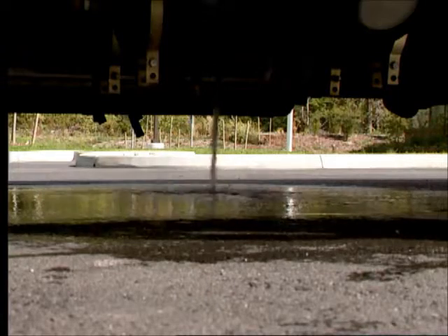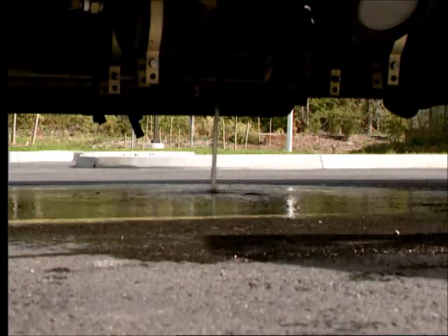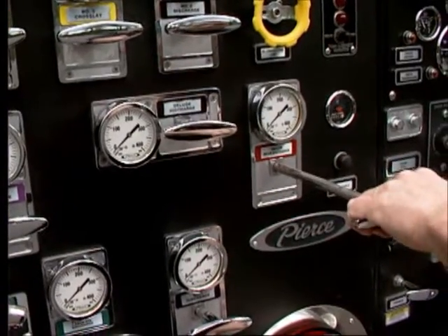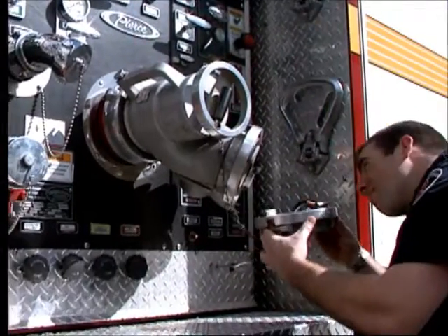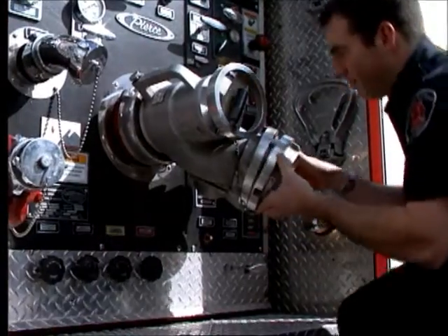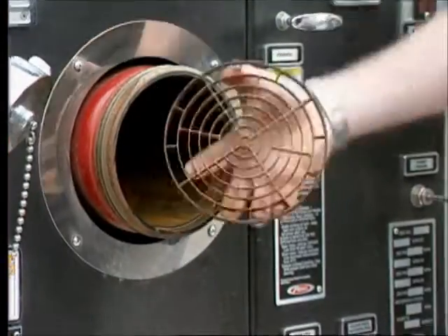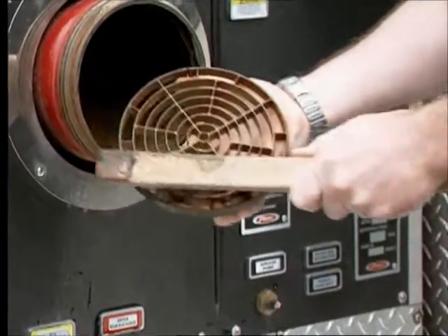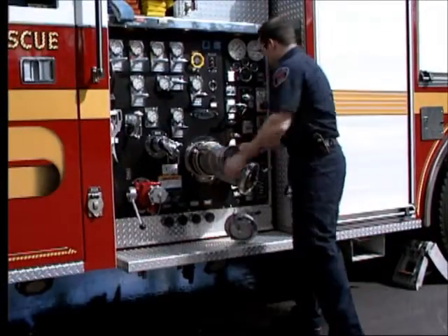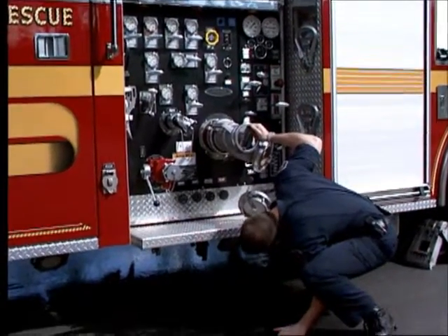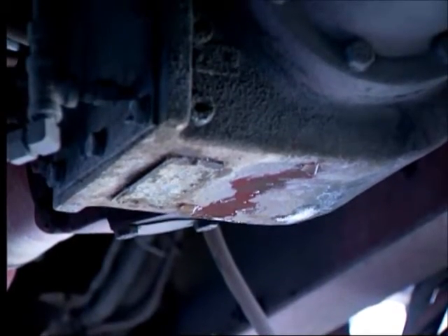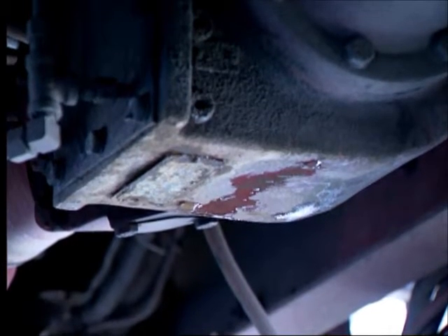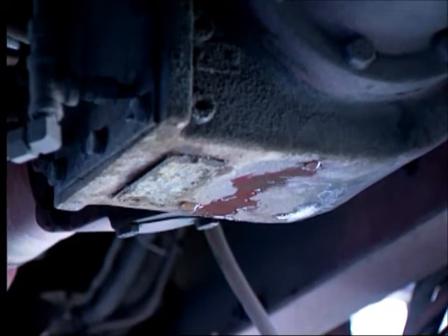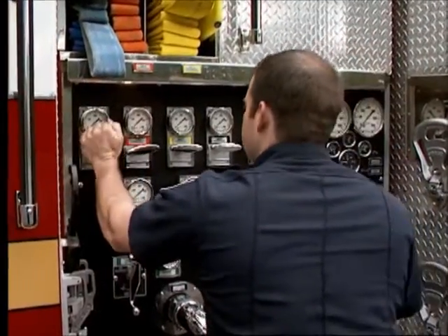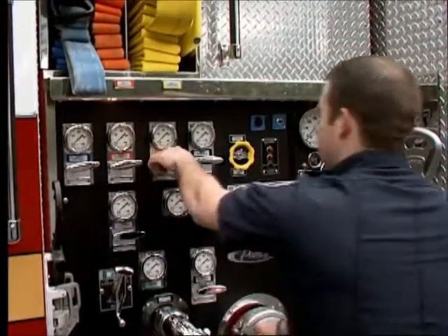If it is your department's policy to carry the pump full of water, it is recommended that you flush it with clear water each week. Check all drains for operation. Be sure that hose connections do not contain any foreign objects that could be drawn into the pump. Clean the intake strainers weekly or after each use. Check the packing glands for excessive leaks. With the pump turning and under pressure, water should be dripping from the packing gland, not running in a steady stream. If you must tighten the packing glands, be sure to follow the manufacturer's recommendations.